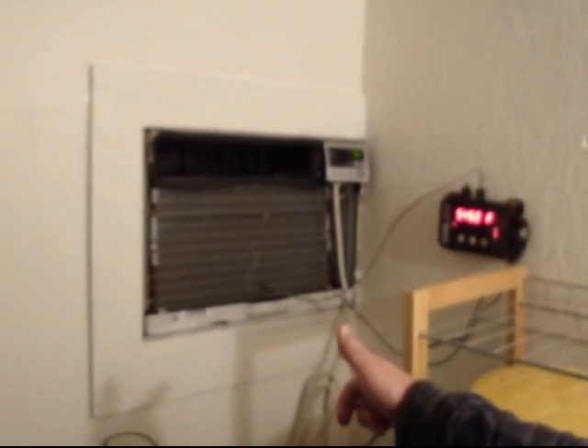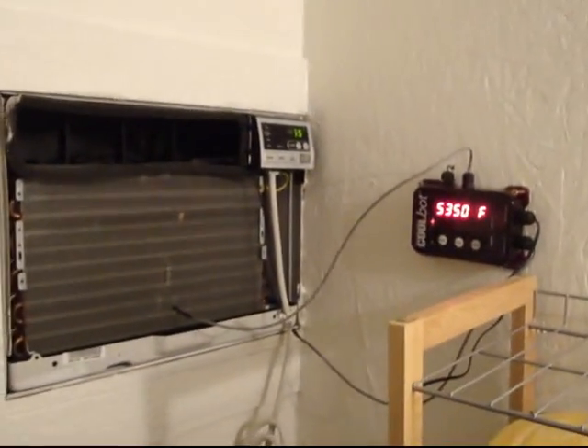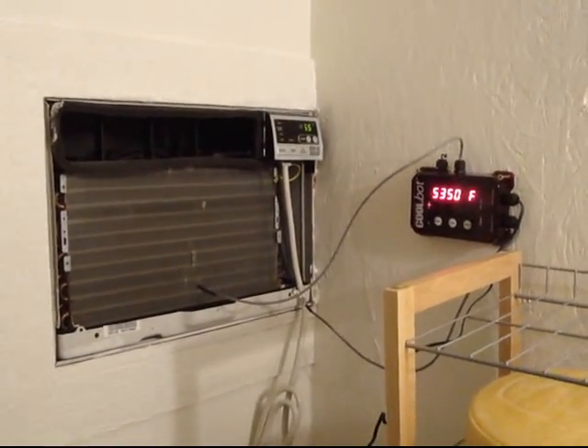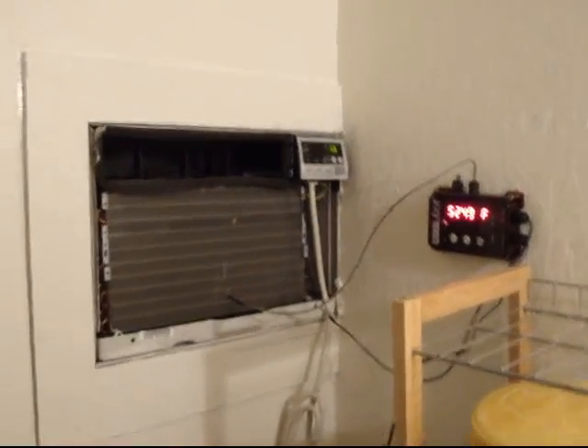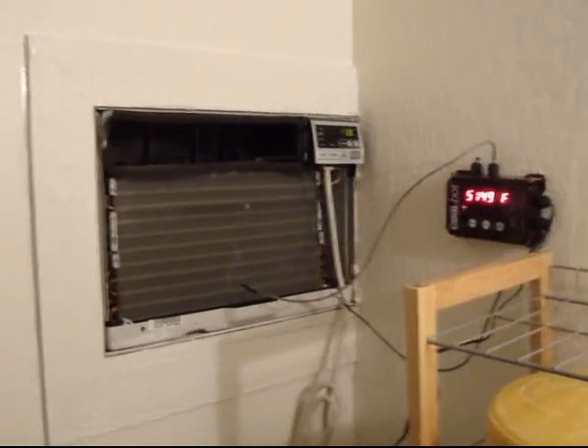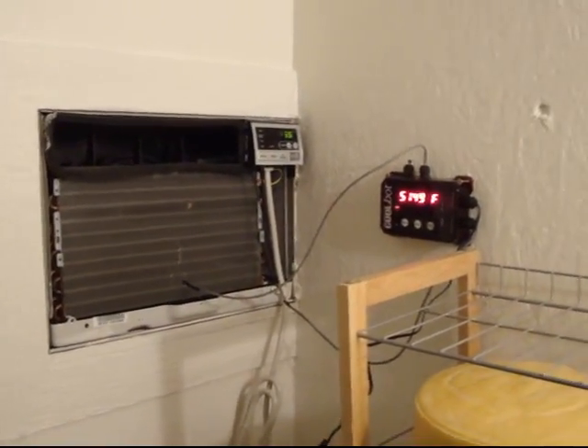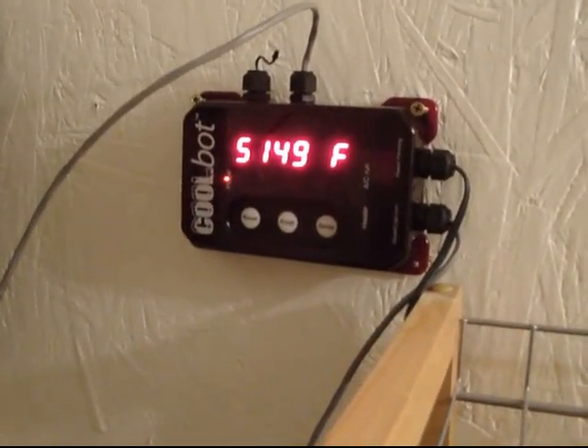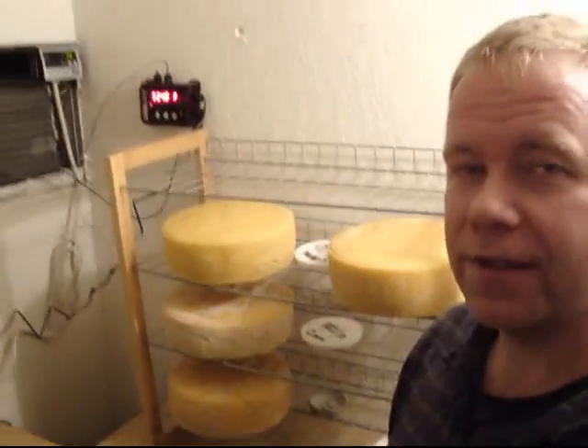The refrigerator came on. So this is a walk-in refrigerator? Yeah. It's just a medium-grade air conditioner, and that's called a CoolBot. It tricks that air conditioner so you can actually take the temperature down to almost 32. This contraption wasn't designed to be a refrigerator — you just outsmarted an air conditioner. That's clever. It's a poor man's cool room.